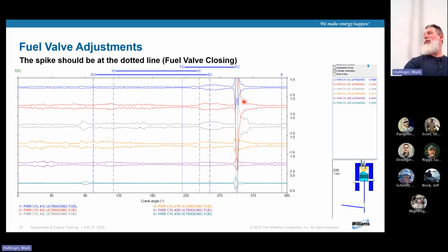So what are these right here? You guys already mentioned fuel valves. What do you notice about the red one? Okay. What about this blue one? It's getting bad. It's chattery? It could be crossed off. Okay. You might have a double tap on that valve and this one's really, really loud.